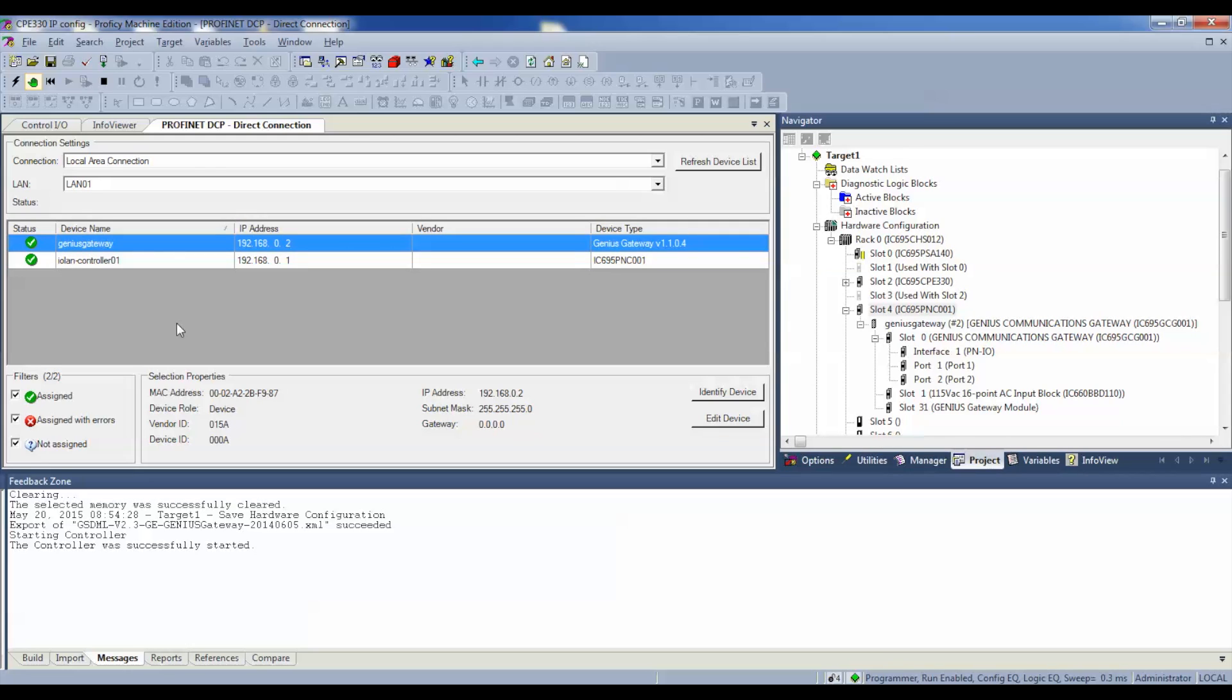So, going back to what I mentioned before about downloading that language, the GSDML. If you've missed that part, when you hit the refresh device list, it's going to continue to search and it won't find anything. Because, it's not talking at the rate that it needs to in order for them to see each other. So, please make sure that you don't skip that step. GSDML. It's found in the GFK 2891A under Configuration Section 3.